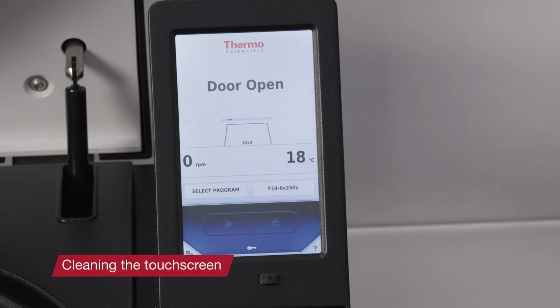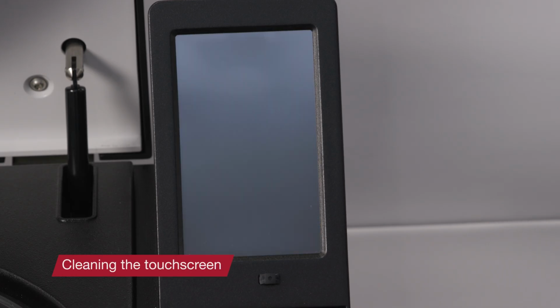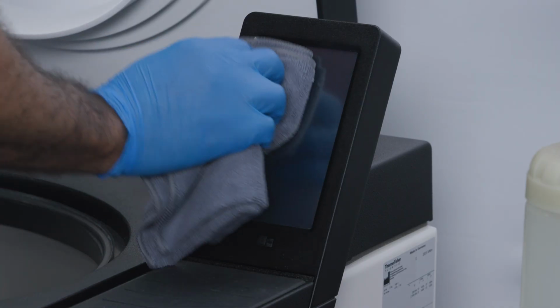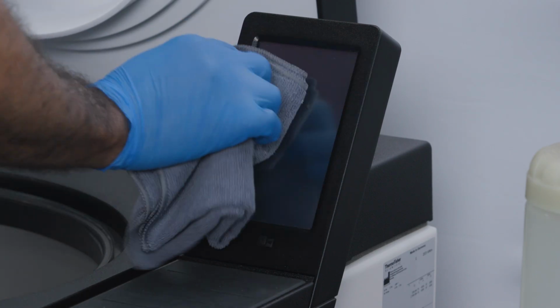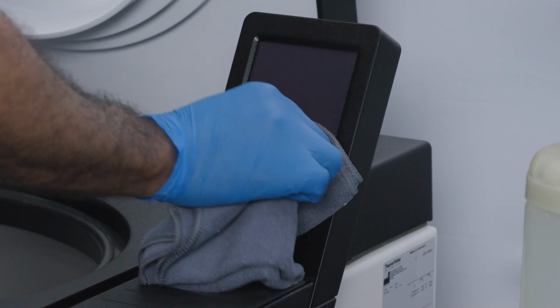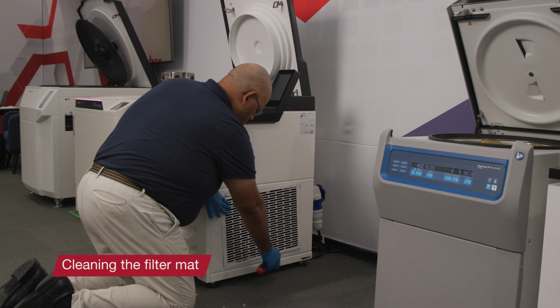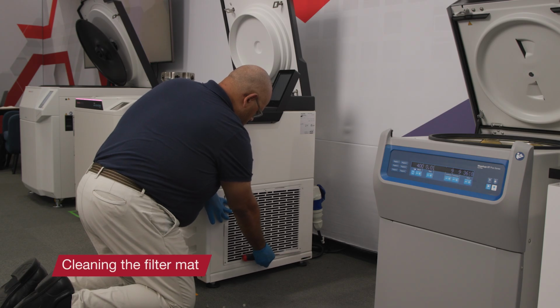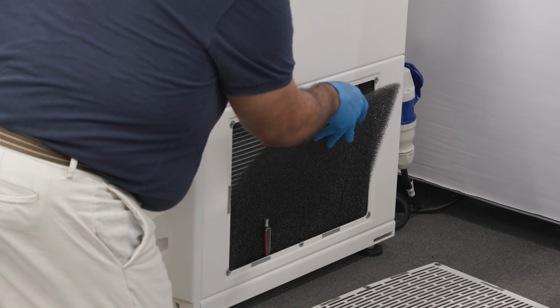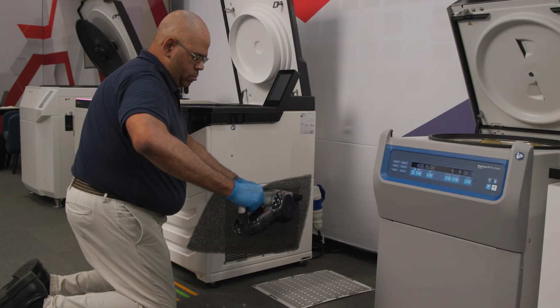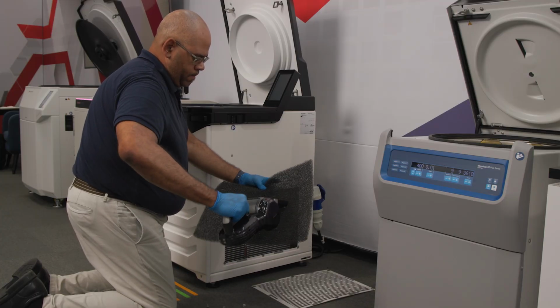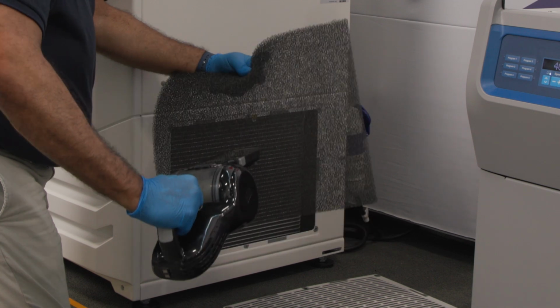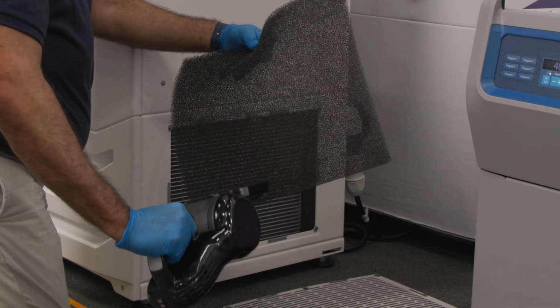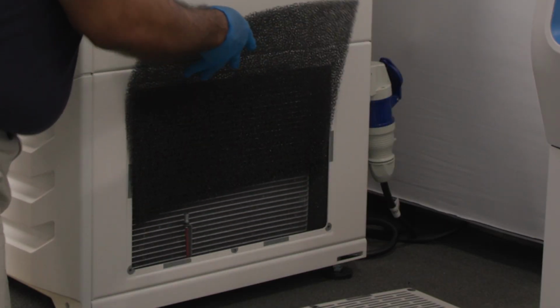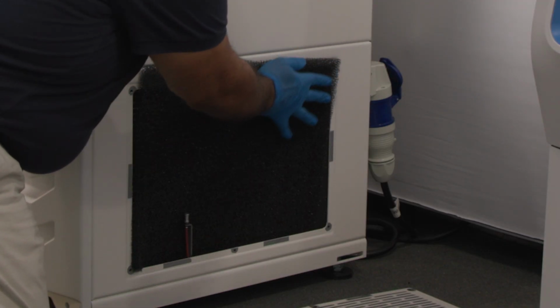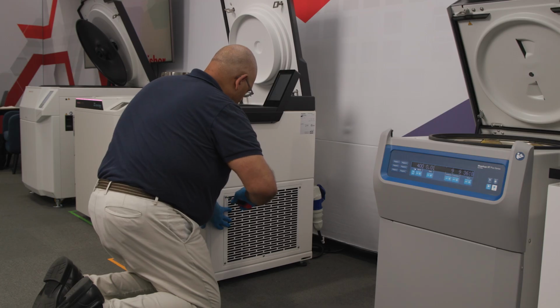To clean the touchscreen, disconnect the centrifuge from power. Clean the touchscreen using a dry microfiber cloth. Moisten the cloth and wipe again if needed. To clean the filter mat, loosen the 6 screws on the venting grid on the right side. Remove the grid and mat and use a vacuum cleaner on both sides. Wear protective gloves while removing and reinstalling the filter mat to protect yourself from sharp edges. Reinstall the filter mat and venting grid and fasten the grid with the 6 screws.